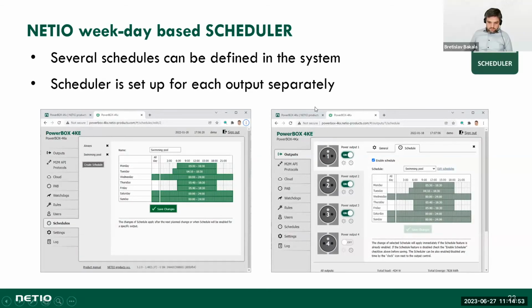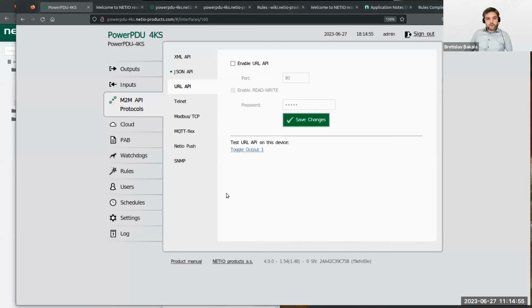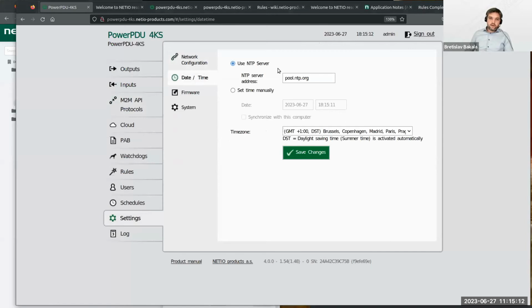Okay, let's switch back again. I will quickly show you how to set up the scheduler. It's in every device. For the scheduler, you need synchronized time, so the device needs to be on the LAN where there's an NTP server. It doesn't have to be internet, but it has to be some local NTP server. You can set it up in the device to your local IP.